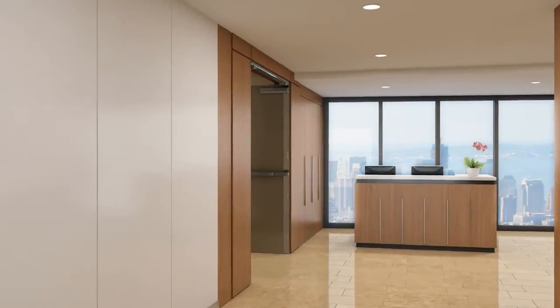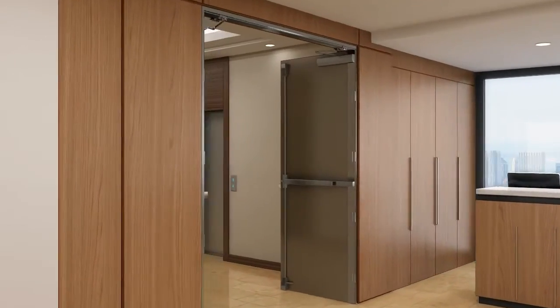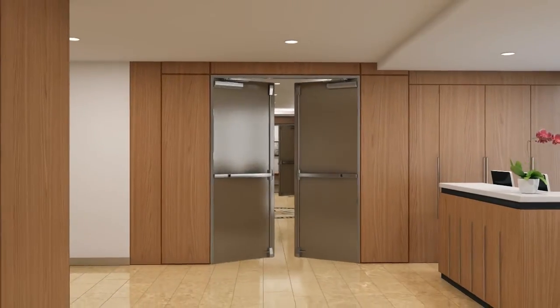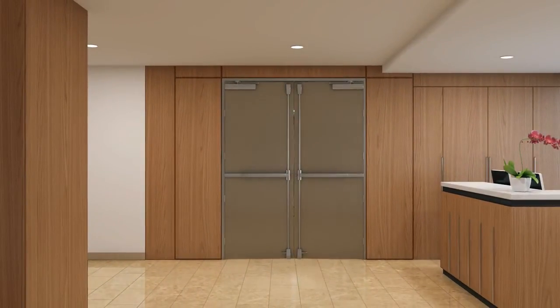The current edition of the International Building Code requires elevator lobbies be protected in all high-rise buildings. A high-rise building is defined as a building with an occupied floor located more than 75 feet above the lowest level of fire department access.